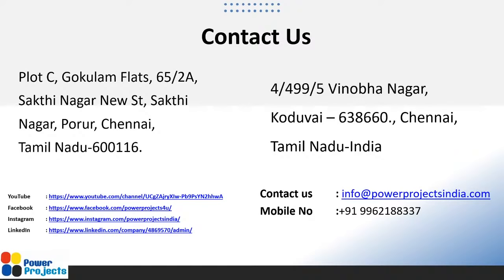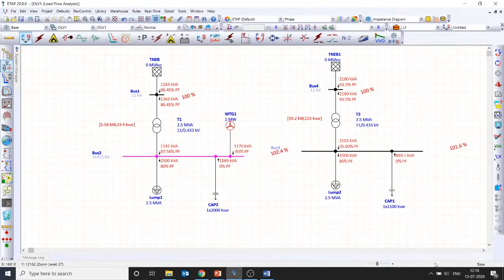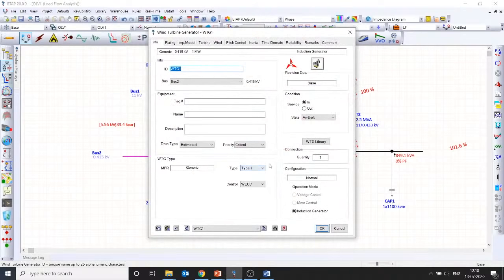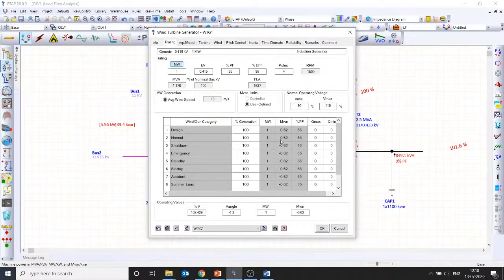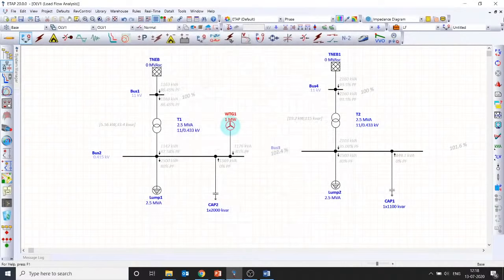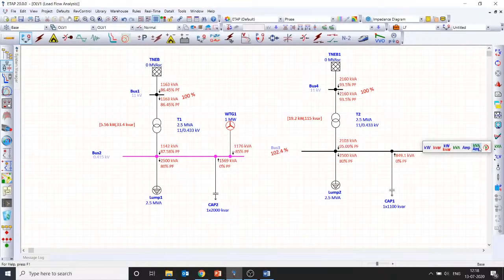Yes, there is a question from Vikrant Tiyaki. Why is the power factor getting so low while adding a wind generation? Thanks for that question, Vikrant. Because we have added a type 1 wind turbine generator, that is a squirrel cage induction generator, that consumes reactive power. Look, when it is generating 1 megawatt, it is consuming 620 kVAr. Yes, when it is injecting 1000 kilowatt, it is consuming 620 kVAr. That's the real reason why the power factor is getting poor.